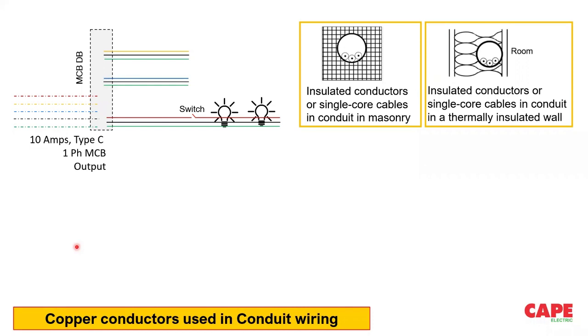Now, IS 732 has included filling factors, derating factors, voltage drop calculations, and several factors with which you can select the appropriate size of the wire. For example, the wire manufacturer may be claiming that a 2.5 square mm wire can handle 20 amps, but practically in your building, you have to use it only for 10 amperes. You cannot use it for 20 amperes because you are pulling it through a conduit, multiple wires are there in the conduit, you have to derate it. These derating factors are given in the standard.